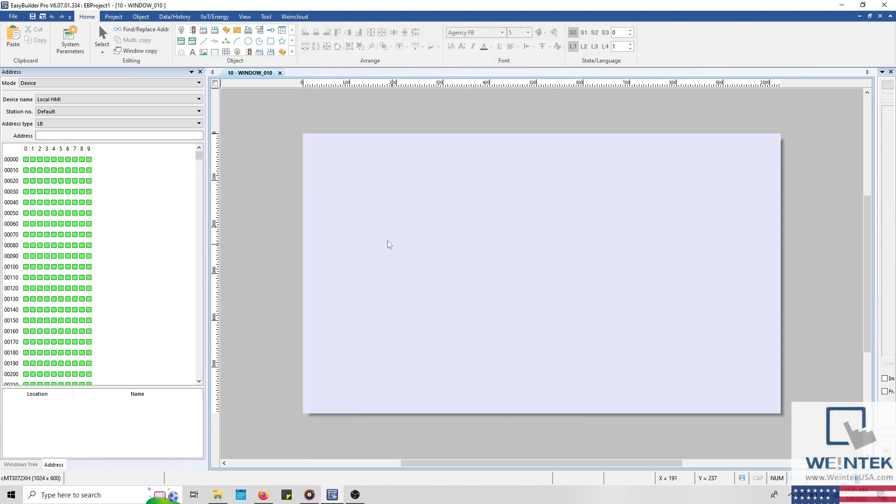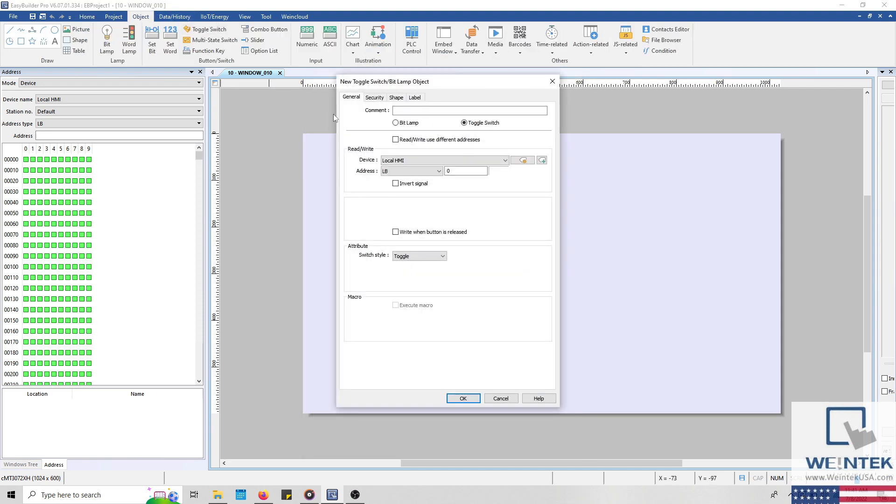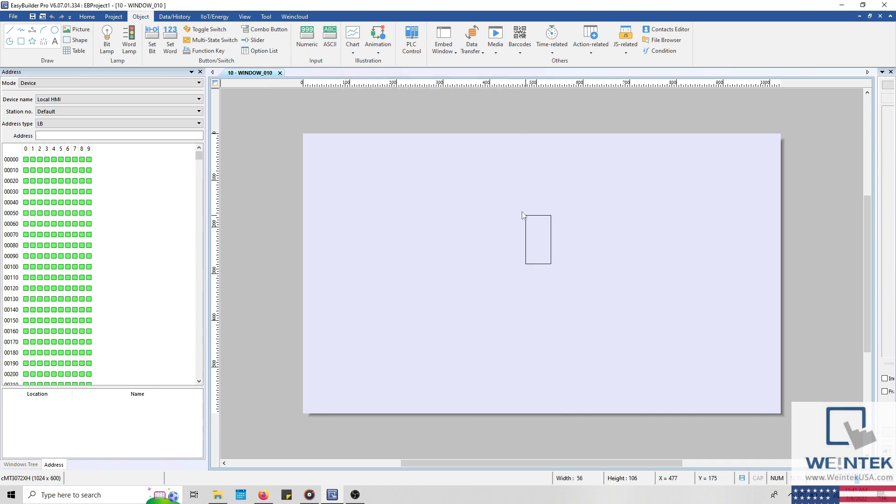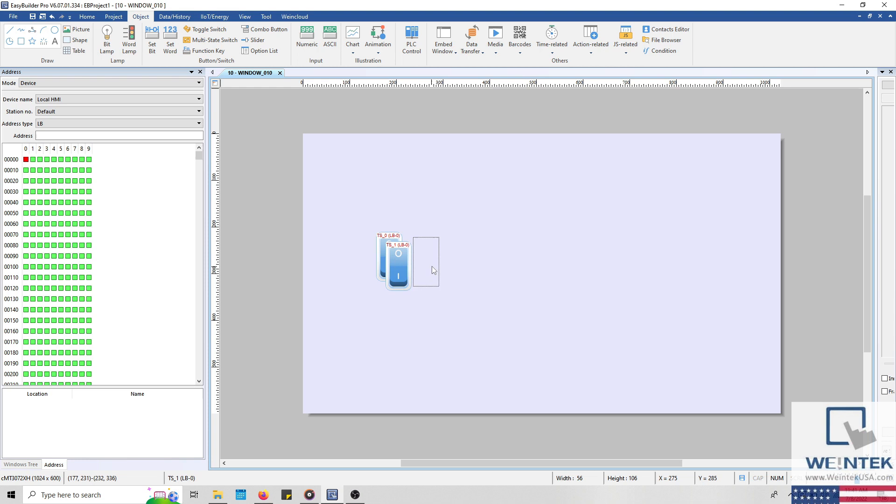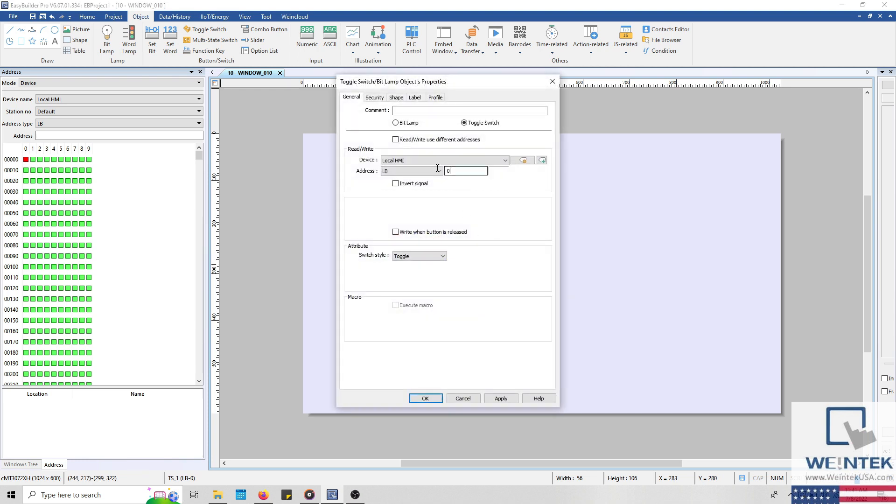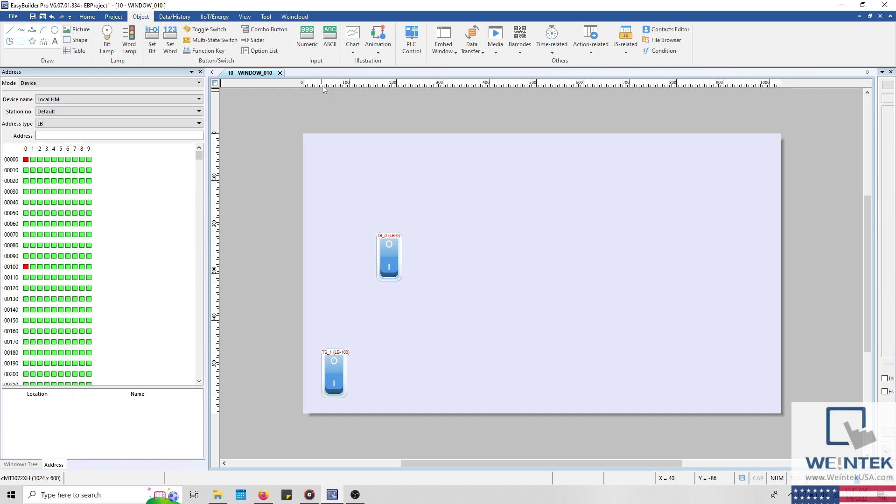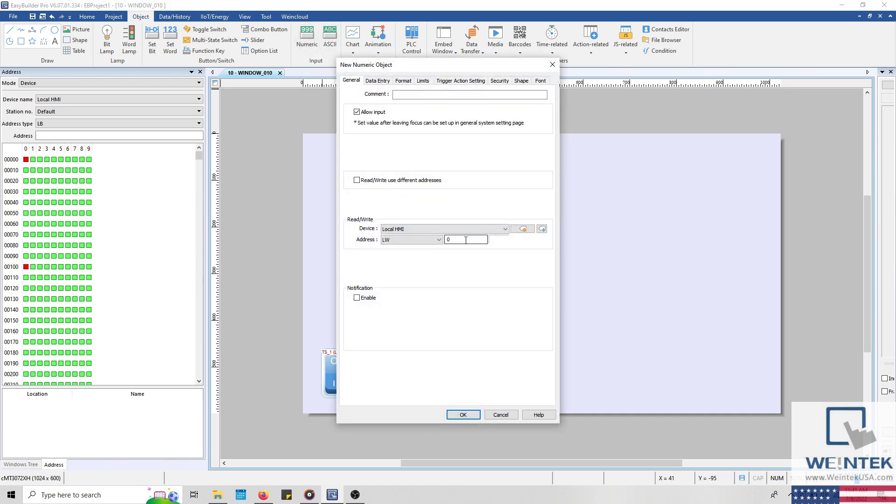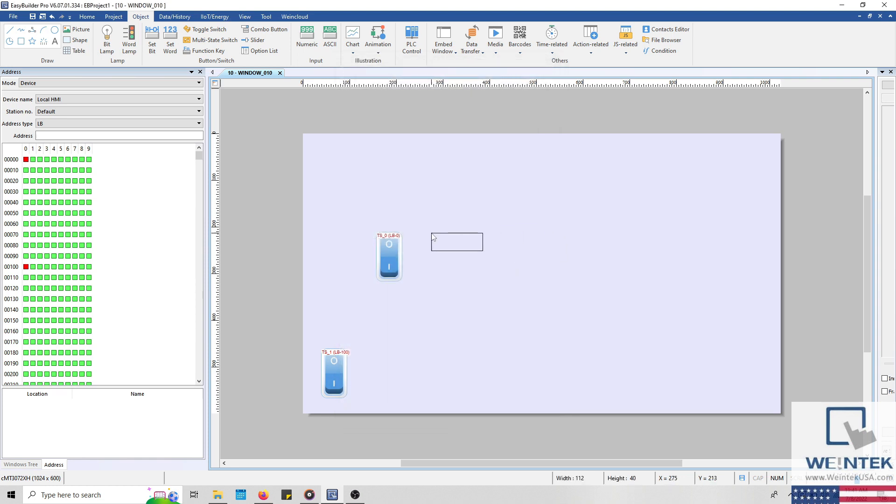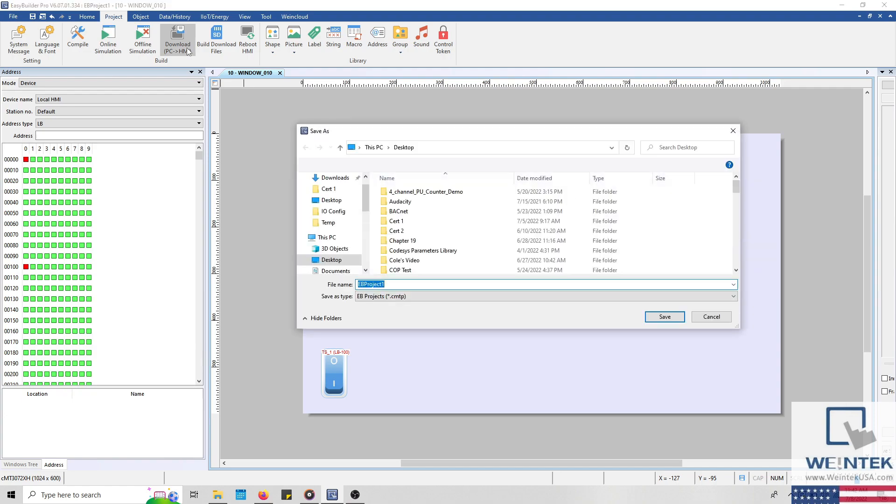With that finished, I'll click OK and place a few objects on our work area. We'll start with the toggle switch, address to LB0. This address is mapped to 0x1 within our Modbus mapping table. And I'll copy this toggle switch, and configure the address to LB100. We'll use this toggle switch to enable or disable write access by toggling our execution bit. I'll also place a numeric object addressed to LW0 on our work area. LW0 is mapped to 4x1 within our Modbus mapping table. I'll leave the rest of my project as is, and download this to our HMI.